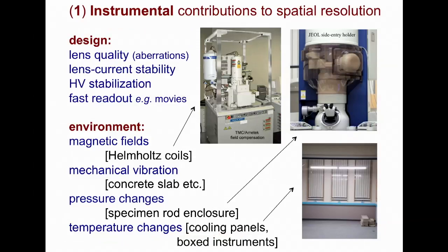In terms of instrument design, improvements in electron optics, including aberration correction, have led to spectacular performance. Improved electronics has also played a big role, including fast readout of spectra and images, which has actually relaxed the stability requirements for power supplies, which were starting to require expensive hand-picked components. But the performance of an electron microscope depends also on the environment in which it operates. It has long been known that low levels of AC magnetic field are needed for high-resolution TEM. Where this is not readily achievable, field sensing devices coupled to Helmholtz coils can be used to compensate for residual fields.